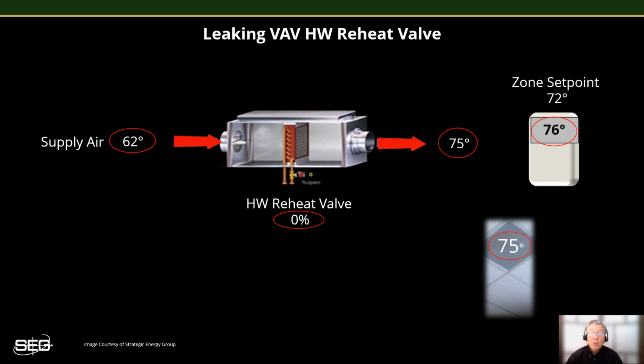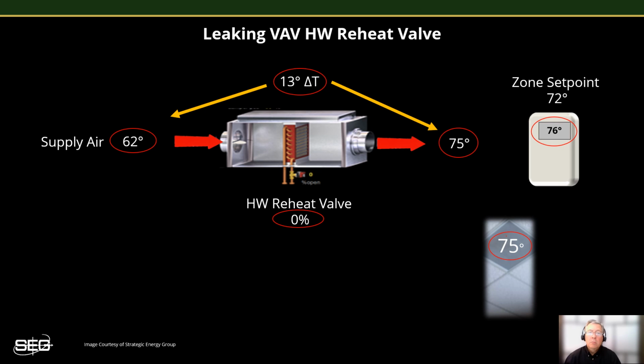Out in the zone, we see that the temperature coming out of the supply diffuser is 75 degrees, which is much warmer than the 62-degree supply air temperature that we would expect to see. So it appears we're getting 13 degrees gain across the terminal box. This pretty much confirms that the reheat valve in this box must be leaking by and will need to be physically checked out for the cause of the problem.